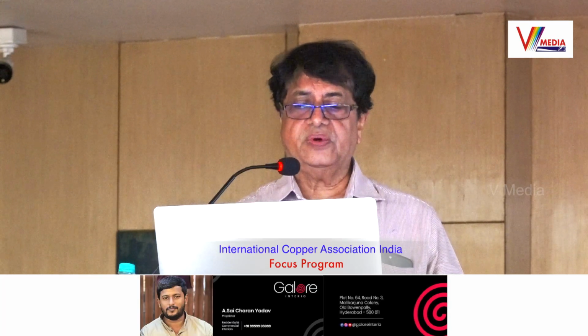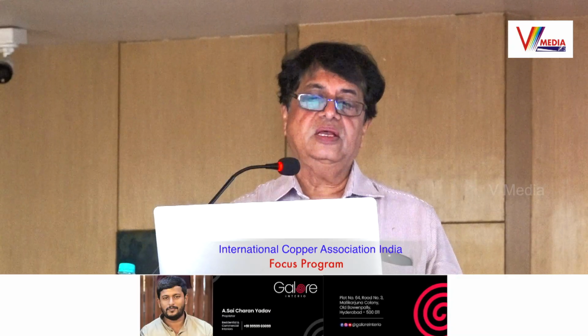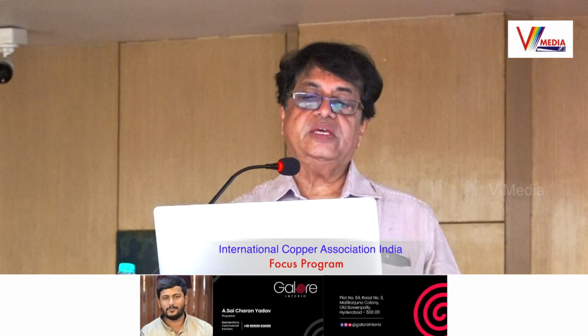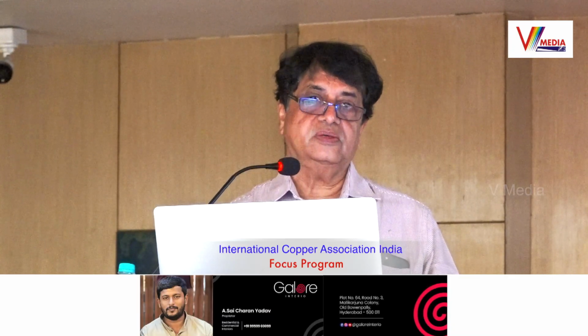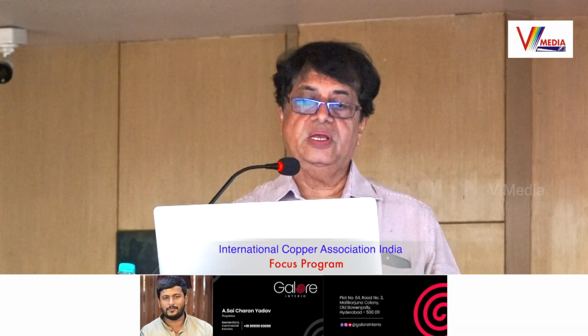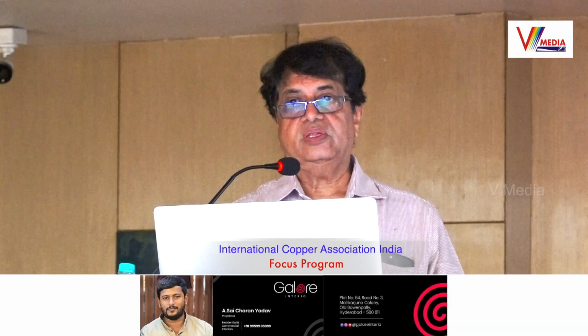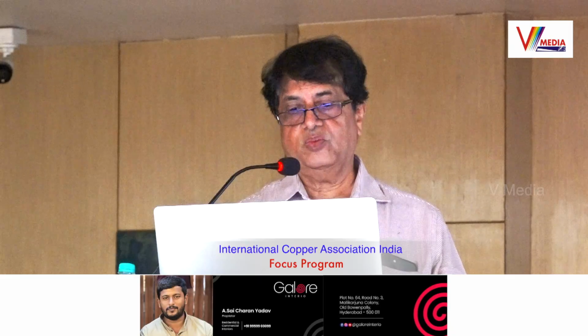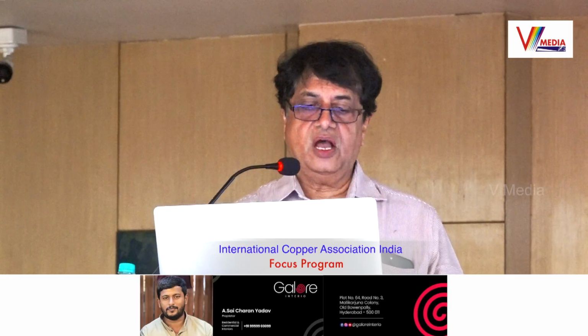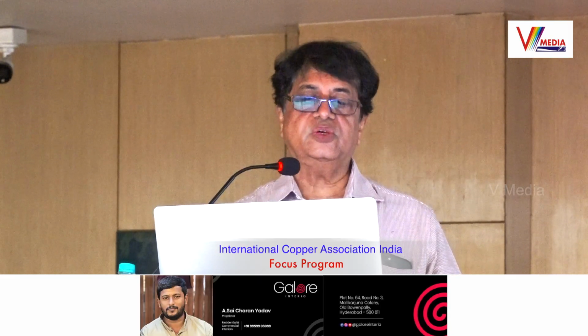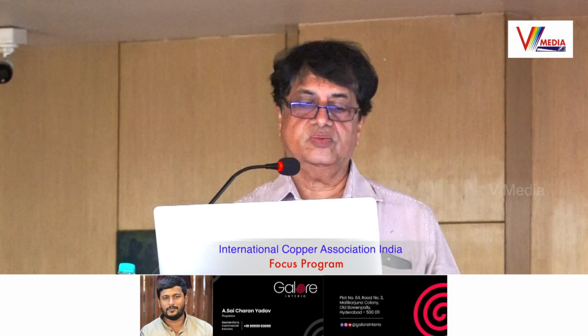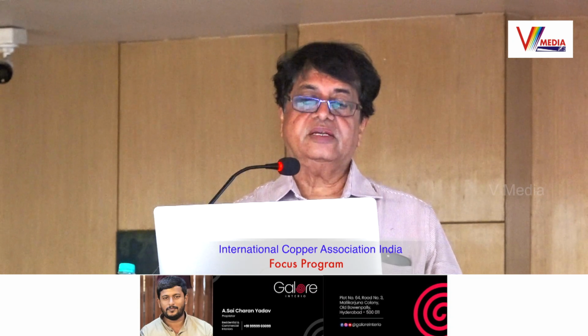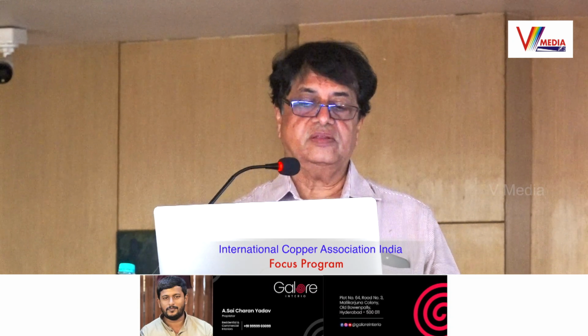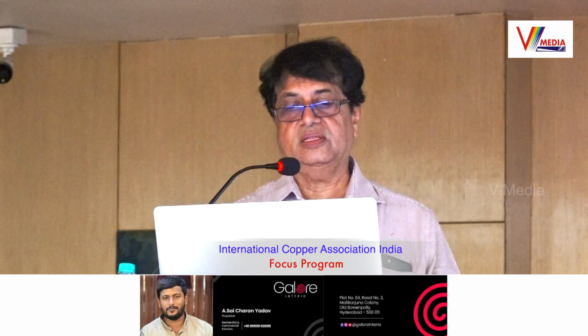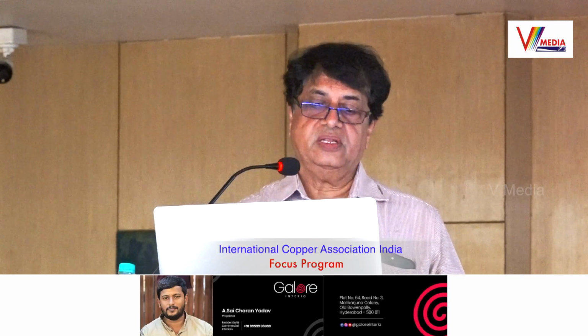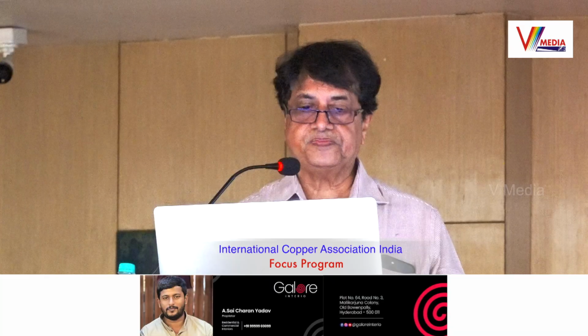This is the picture of an exhaust fan which is burned. Why does an exhaust fan burn? Again, if there is no fresh air intake arrangement for that particular envelope, it may lead to negative pressure and your fan motor gets burned. See here how the arrangement can be made. Suppose it is a washroom or restroom door; a certain intake arrangement is made at the bottom where fresh air can come in. So there will be continuous change of air and there won't be any negative pressure.